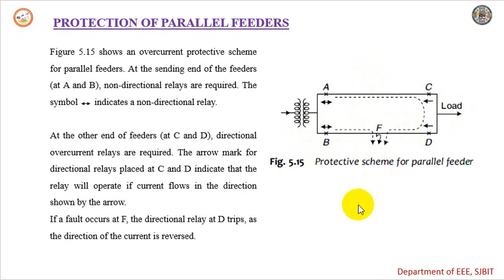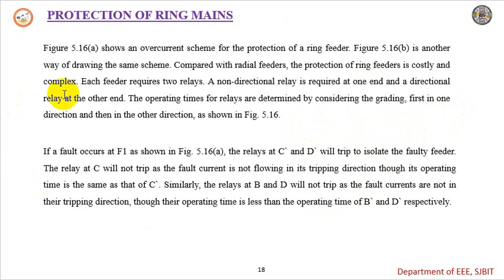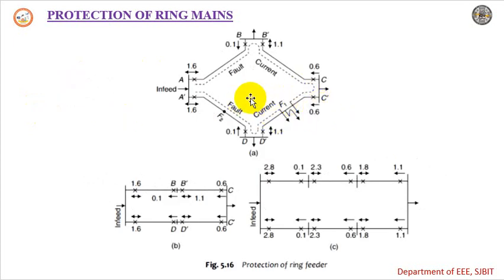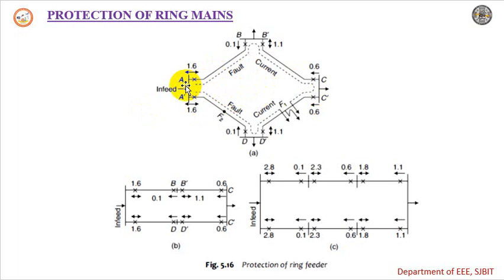This is how parallel feeders are protected. Next we have the protection of ring mains. Looking at the ring main diagram, here we have four feeders. The overcurrent scheme for the protection of the ring feeder is shown. For every feeder, there is one non-directional relay and one directional relay — this pattern repeats for each feeder section in the ring.